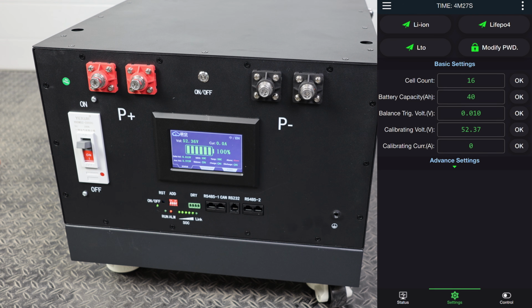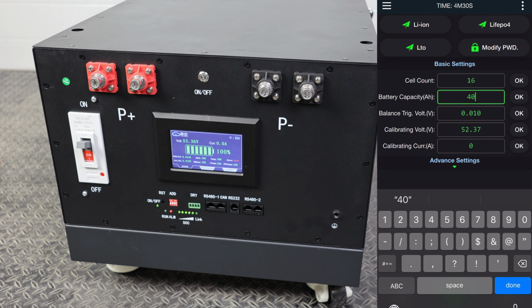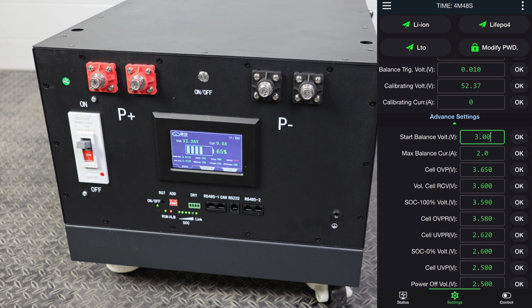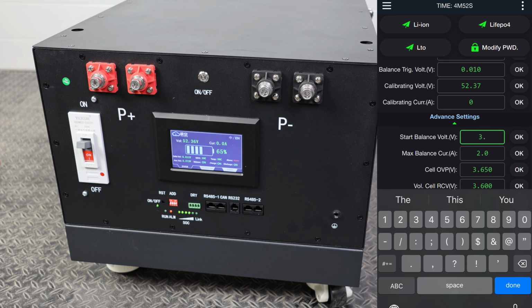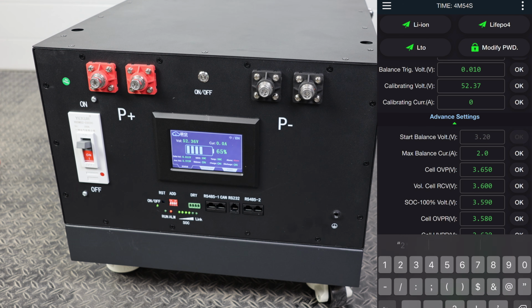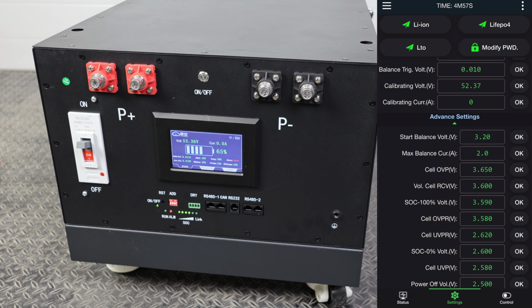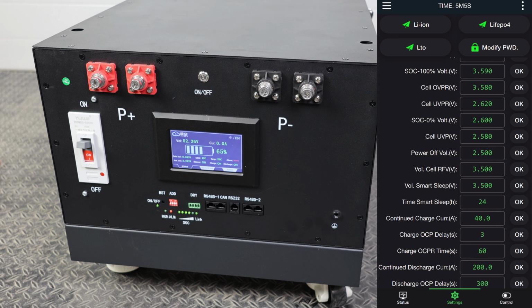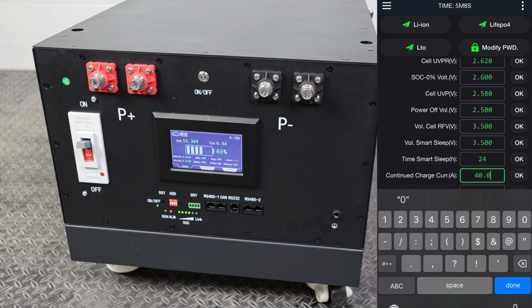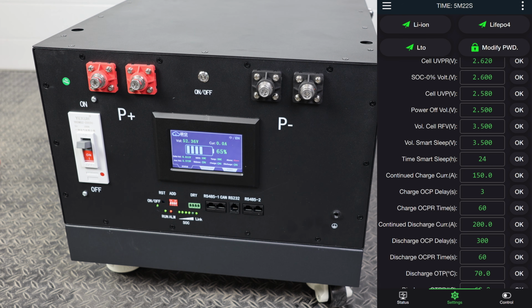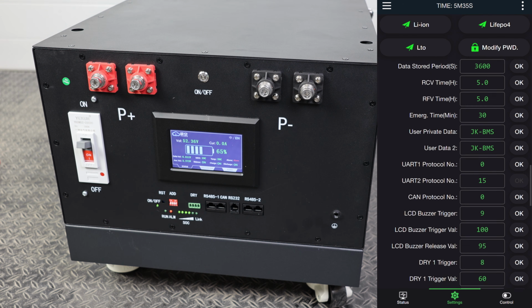That should put in the base settings for us. We have 16 cells, so let's change the battery capacity to 314 amp hour. Let's bump the balance voltage up to 3.2. Max balance current of 2 is okay. And for max continuous charge current, we want to change that to 150 amps—40 would be way too small for what we want to do here. The rest of those settings I think are okay for now.